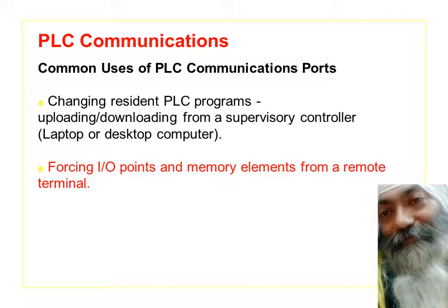There is one thing called forcing IO points and memory elements from a remote terminal. It means that I may not be sitting at the point where the PLC is controlling the process. I may be sitting remotely. Remotely means I may be sitting two continents apart. That's not going to matter. I can specifically make one particular input or one particular output on or off. I can read the memory. I can write the memory remotely as and when required. For that, special access is to be given.